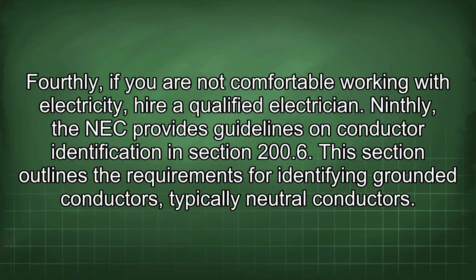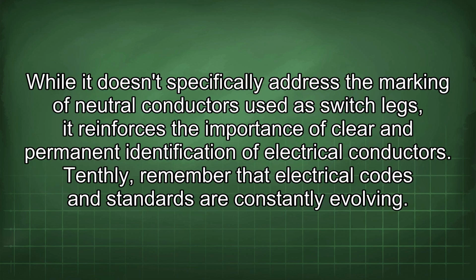Ninthly, the NEC provides guidelines on conductor identification in Section 200.6. This section outlines the requirements for identifying grounded conductors, typically neutral conductors. While it doesn't specifically address the marking of neutral conductors used as switch legs, it reinforces the importance of clear and permanent identification of electrical conductors.